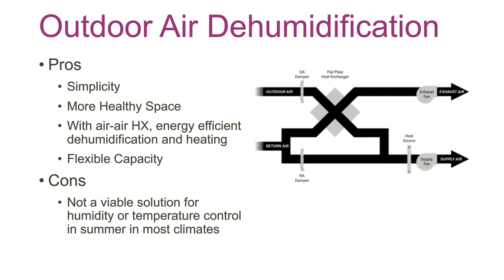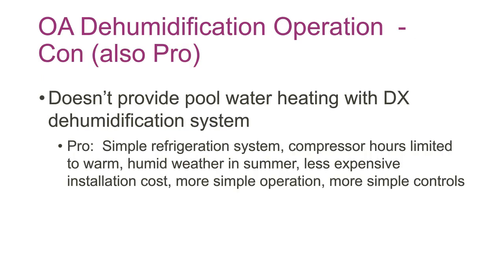The cons of the system we're showing here is that you can't control summer humidity in most climates with this, because at some point the outside air becomes too humid to do it. And it's usually around a 63 to 64 degree dew point outside, by the way. You don't have to get all the way to the dew point of the space before 100% fresh air won't do the job. So the downside really is we're not addressing pool water heating. With that type of a system, you heat pool water separately with as efficient pool water heater as you can.